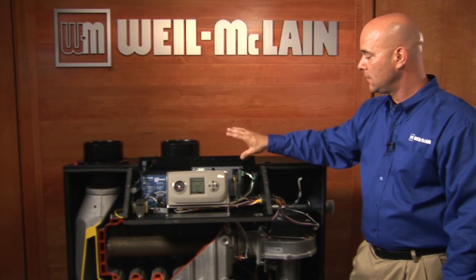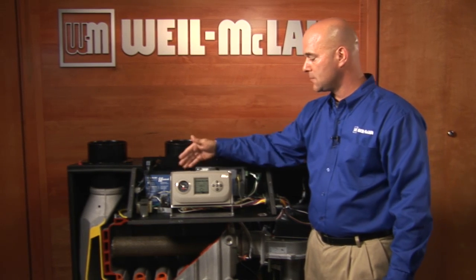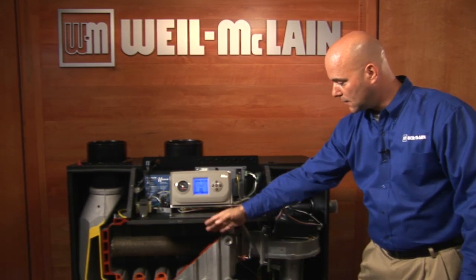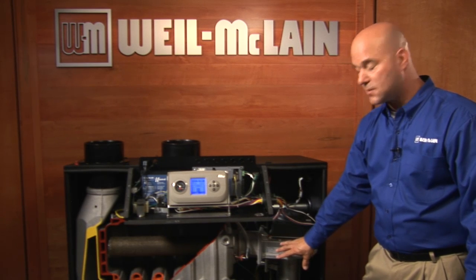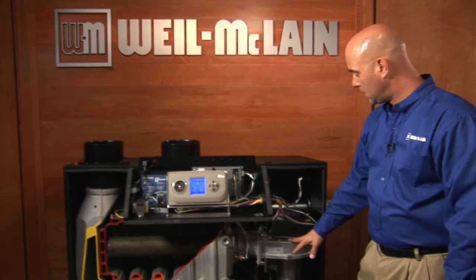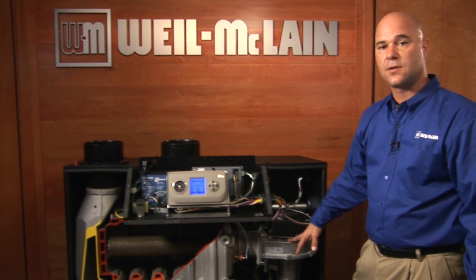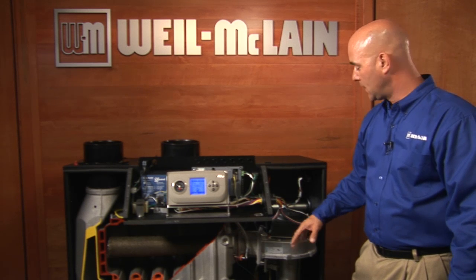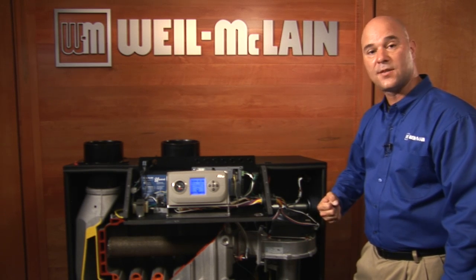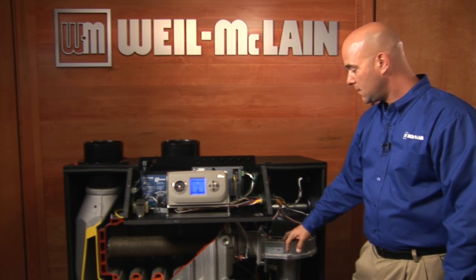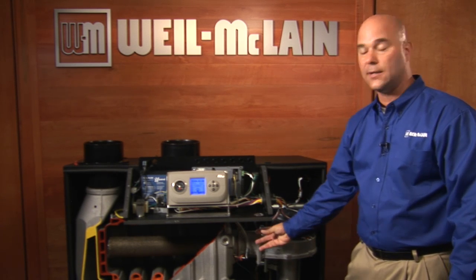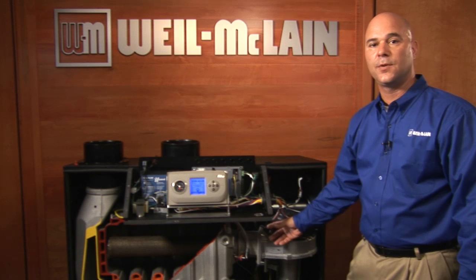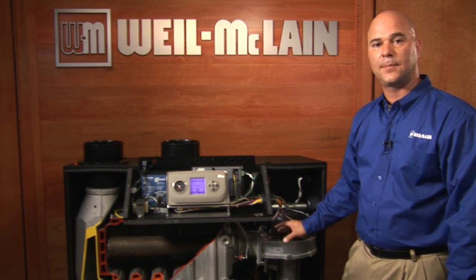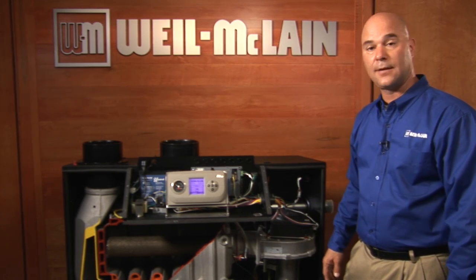fresh air inlets, to the U-control, to the expansion module, to the display module, to the heat exchanger, and all the components that work in conjunction with the combustion blower. We're still using a negative pressure gas valve. We're relying on the boiler to draw its gas through the gas valve, mix it in the combustion blower, and inject it in. Same technology we use on the residential model. We've just stepped it up to a larger boiler and use it on the commercial version.